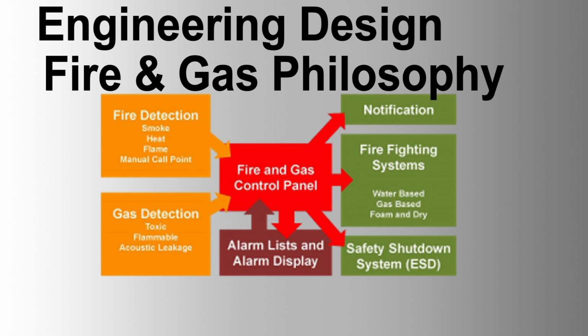Fire and gas executive logics. Fire and gas executive actions for shutdown and alarm are based on the fire and gas philosophy document. The logic initiates alarms upon detecting abnormal conditions, prevents incident escalation, and avoids unnecessary shutdowns due to spurious events. General rules include configuring logics as non-fail-safe and energized to trip. No time lag between causes and effects unless specified. Providing maintenance override for each initiator with a permissive override enable switch. Confirmed detection requires multiple activations of flame, gas, and manual initiation devices as detailed in the fire and gas cause and effect matrices.